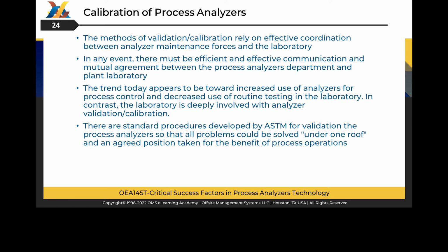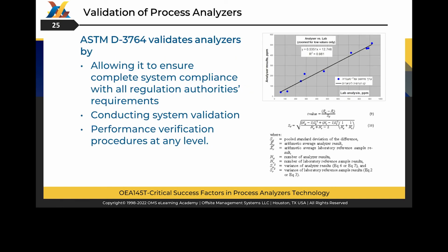The methods of validation calibration rely on effective coordination between analyzer maintenance forces and the laboratory. Therefore, there must be efficient and effective communication and mutual agreement between the process analyzers department and the plant laboratory. ASTM develops standard procedures to validate the process analyzers so that all problems could be solved, quote-unquote, under one roof, and an agreed position taken to benefit process operations.